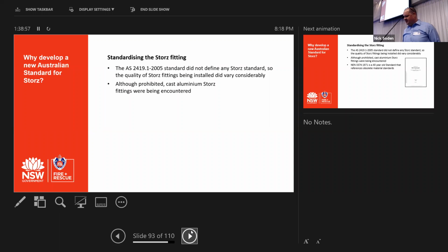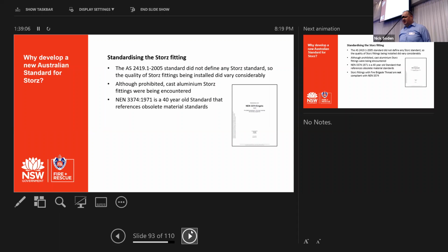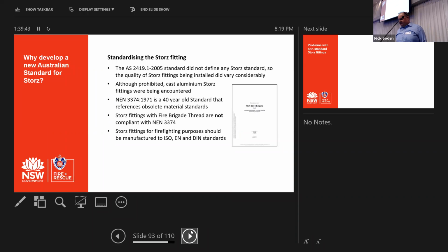Although prohibited in Part 1, cast aluminium Storz fittings were being accepted. Now, NEN 3374, which you probably heard, is a 1971 standard from the Netherlands, and it references obsolete material standards. So while there was a standard being referenced, it was out of date. And Storz fittings with fire brigade thread are not compliant with NEN 3374. So quite often you'll see a fire brigade booster or fire hydrant valve and it'll actually have a Storz fitting on it. But if it's got fire brigade thread, then it is not technically a NEN 3374 compliant Storz. Storz fittings for fibre gauge for firefighting purposes should be manufactured to ISO, EN and DIN standards. So the original intent of the NEN standard was to comply with European standards, but as I said, they were made obsolete, and because the standard hadn't been updated, the references have been lost.